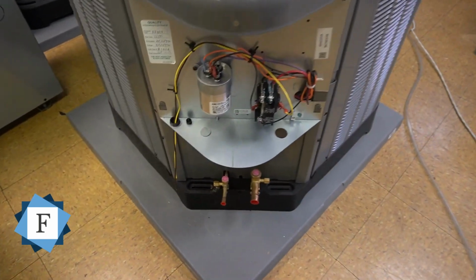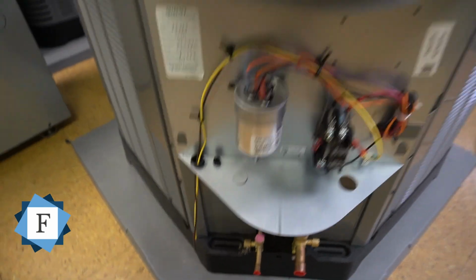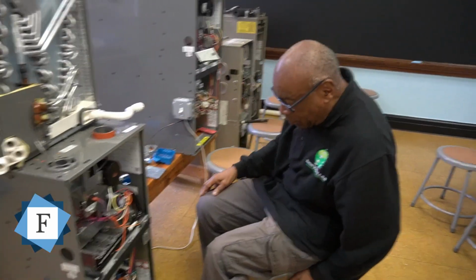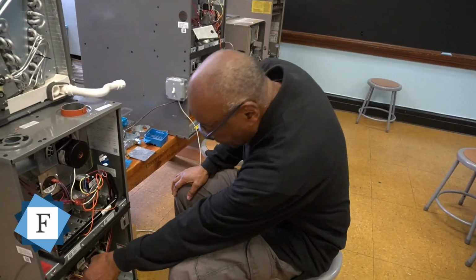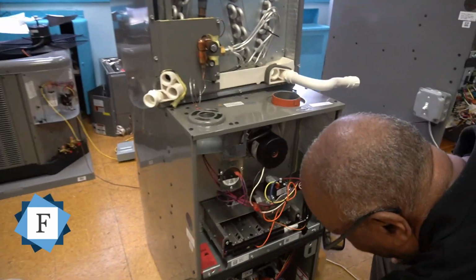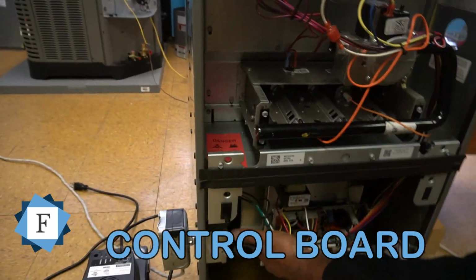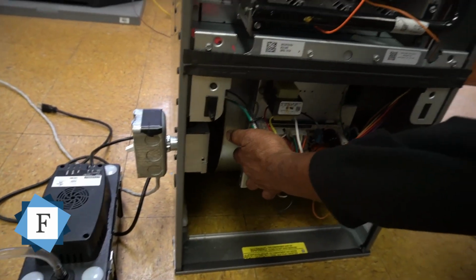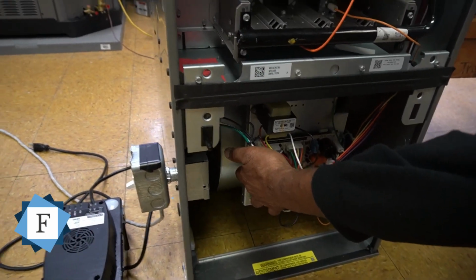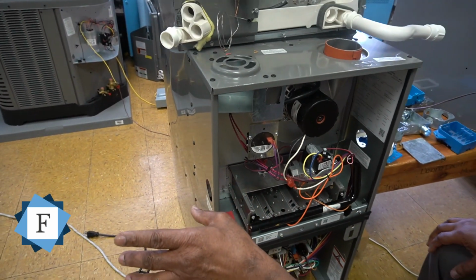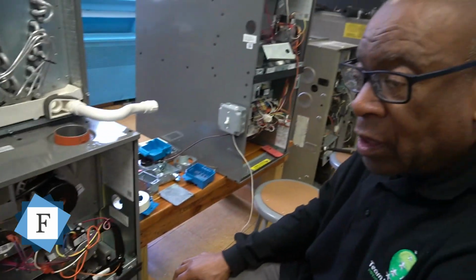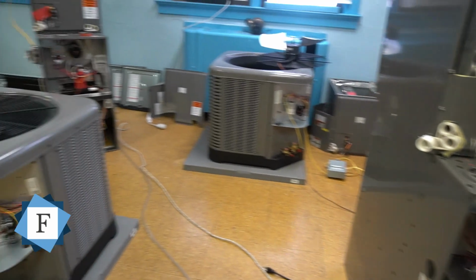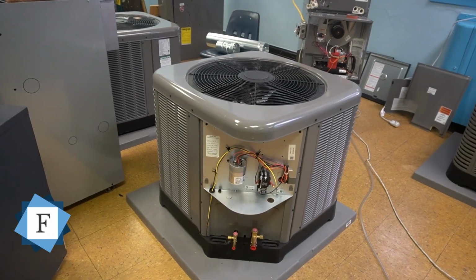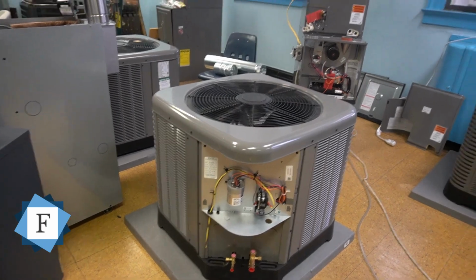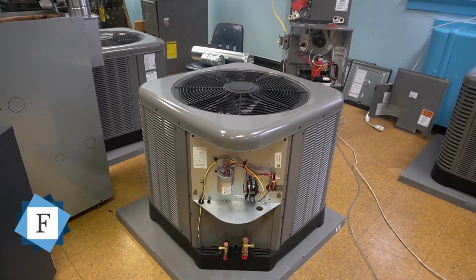And the last component I'm going to discuss today is, not the last, but we also forgot to mention the low voltage side here. This is our control board here. This is the control board, and you have 24 volts, and your cable is running from here to outside at the condensing unit, and that's what turns on the contactor that enables the fan and the compressor to turn on with help of the capacitor to start it. That's the whole cycle of your refrigeration system.